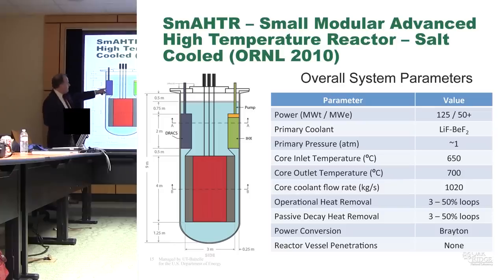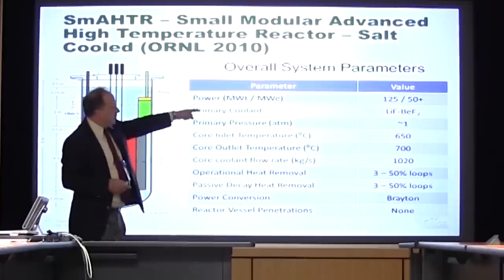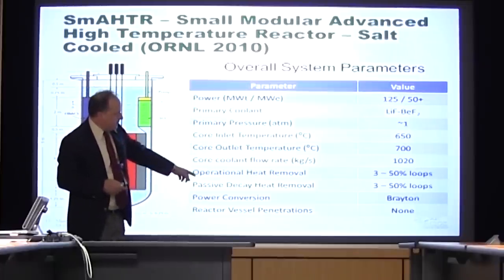It's a graphite moderated core with TRISO fuel and FLiBe coolant. It's an integral design with integral primary heat exchangers and decay heat removal heat exchangers. It's 125 megawatts. It would use FLiBe, atmospheric — all the benefits of salt. It's got redundant heat removal systems and Brayton power conversion. This would be a small modular salt-cooled reactor.